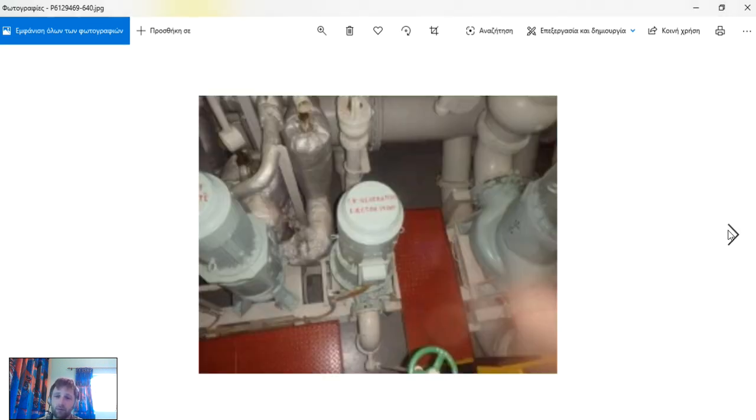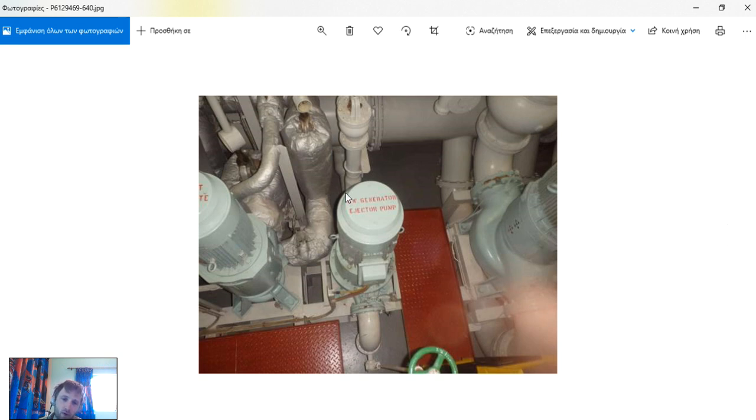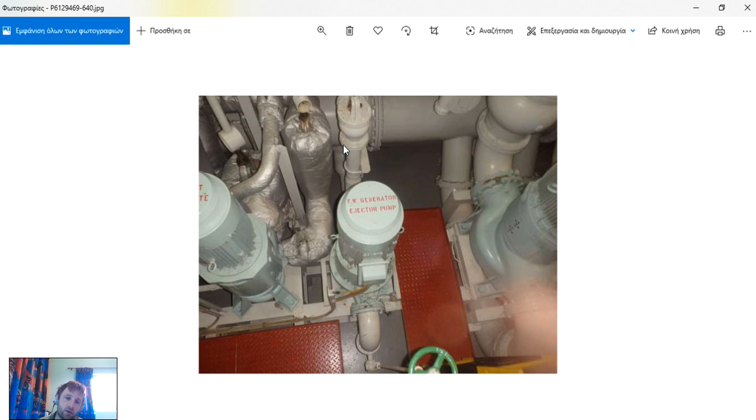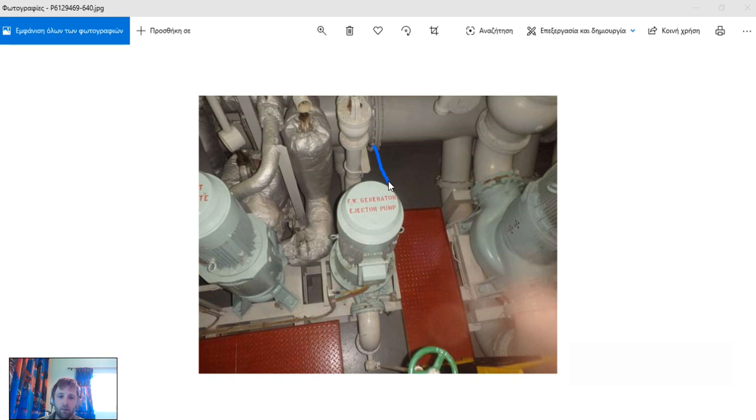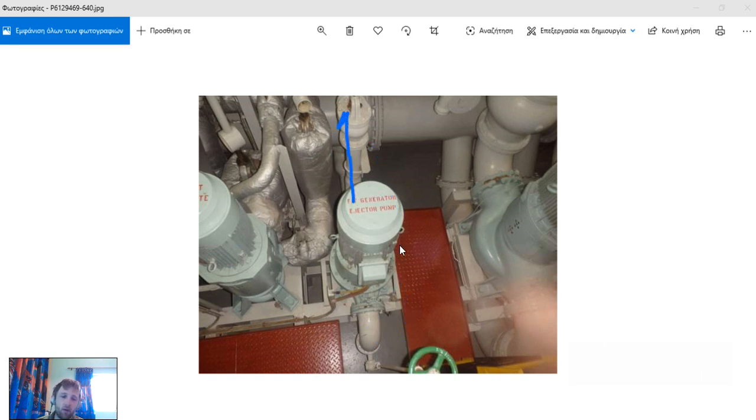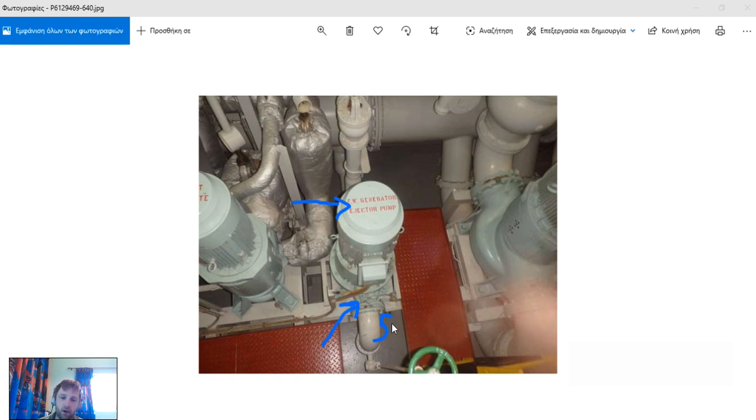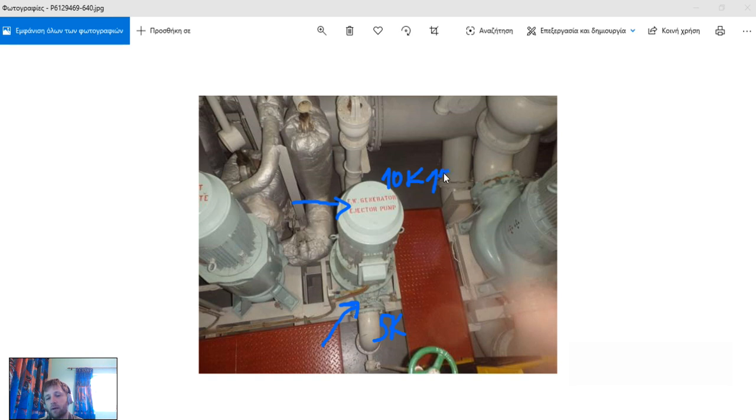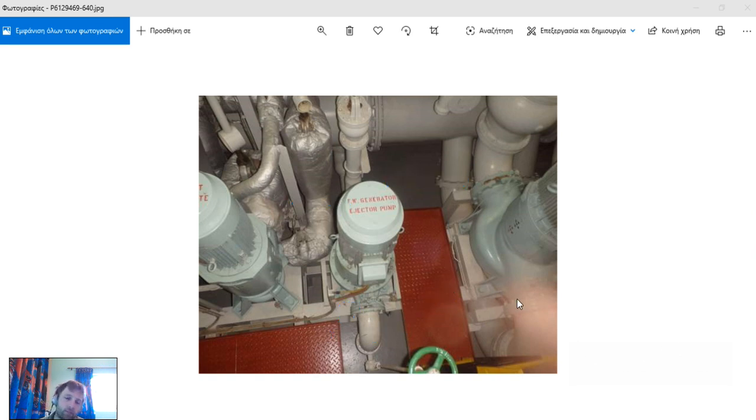We have also our fresh water generator ejector pumps here. There is only one pump. The suction comes down below here, passing down the pump and coming here. This is the suction pipe here and the delivery. We have a difference in the flanges here - there is a different flange because in the suction we have 5K flange and here we have 10K flange. I don't remember the exact diameter but it's different, something like 150 and here it's 125 if I remember properly.